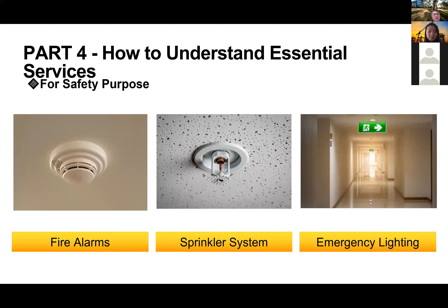For safety purposes: fire alarms give notice of smoke or fire, sprinkler systems, and emergency lighting. All these are must-haves in any type of building except residential. Residential only requires a fire alarm, but sprinkler systems are required in commercial buildings — class two to nine. Emergency lighting is also required in class two to nine.